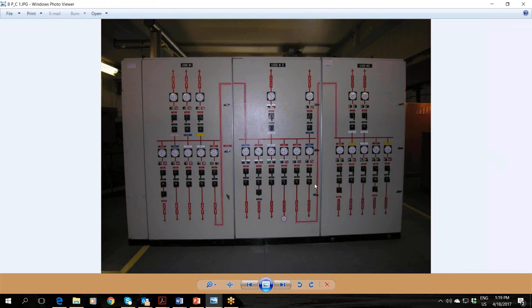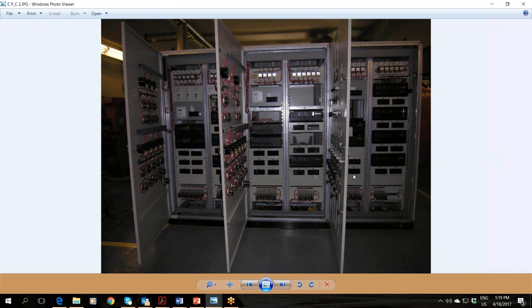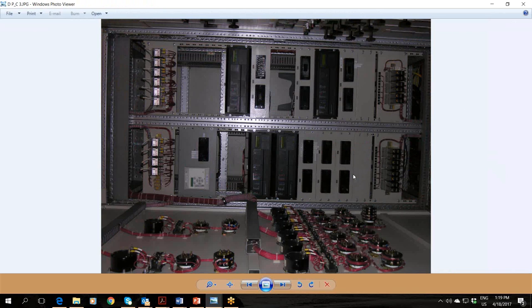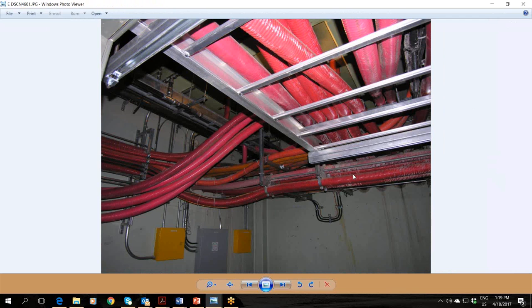So this is a picture of our protection and control cabinets. As you can see, pistol grips and lockouts and amp readings, all those kinds of things. You open the doors, you see all the different protective relays and FT switches and whatnot. So again, we just like to keep that remote from the switchgear. It's one of the things that we can do around arc flash. Again, you don't have to have people there that are interacting with relays, that are doing testing for the relays, or the communications associated with those relays. So just another photo of the protection and control cabinet for the south switching station.